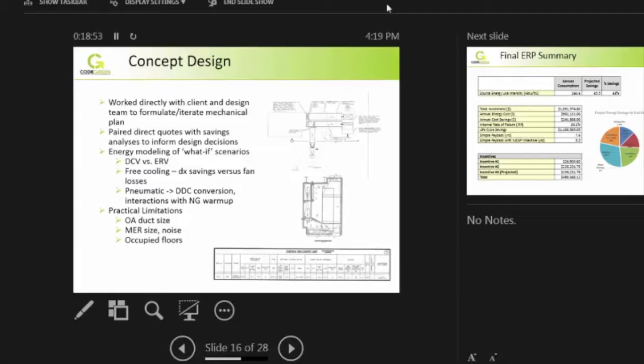Free cooling — we also looked at the additional pressure drop across the fan, especially in buildings with very long operating hours where the fan runs overnight. You may offset a lot of your free cooling water side economizer savings just with increased fan energy usage. That's another thing we took into consideration, along with practical limitations like room size that we had to work through on a real MEP project like this.